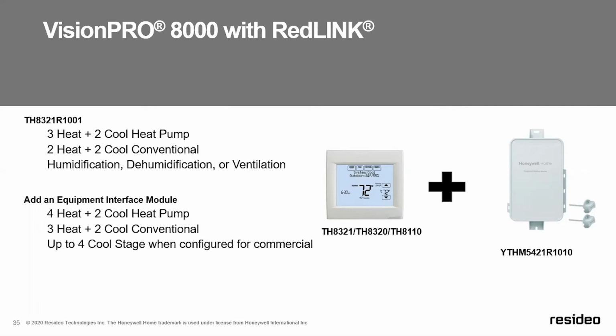Additionally, if you decide to add the equipment interface module, now you have what I refer to as the Swiss Army knife of thermostats. Your thermostat itself could be wireless, communicating to the equipment module in your equipment room, or the thermostat could be wired with 2 wires for power so you don't have to worry about batteries, and then communicate to that module where you have the ability of having 4 heat, 2 cool heat pump control, 3 heat, 2 cool conventional system control, and additional cooling stages up to 4, or configured as a commercial stat, and add to that the ability to control HUME, DEHUME, and ventilation all at once from one device. So truly the most flexible and versatile thermostat option that we have available.